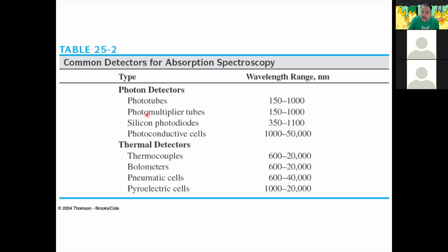Silicon photodiodes, not so much these days, except for 2 applications. One is if you're doing single molecule detection. In that case, you're taking a photodiode and basically running it backwards, to the point where just the tiniest little bit of energy is going to cause that thing to break down and conduct. And then you will see them as diode array detectors in really just chromatography.